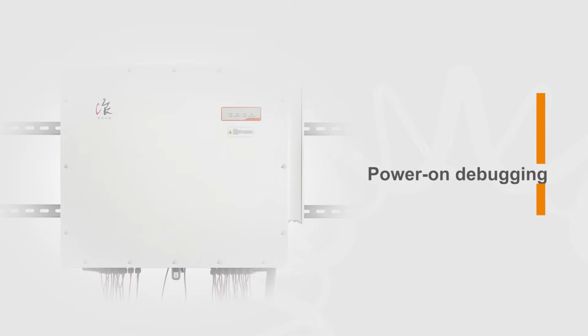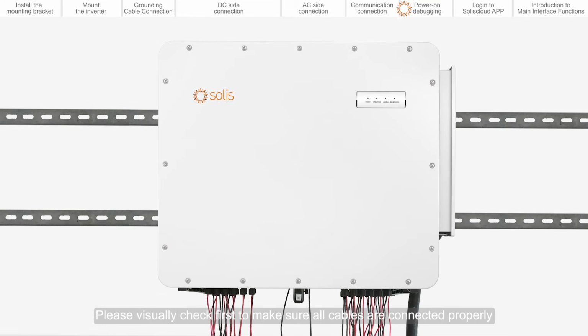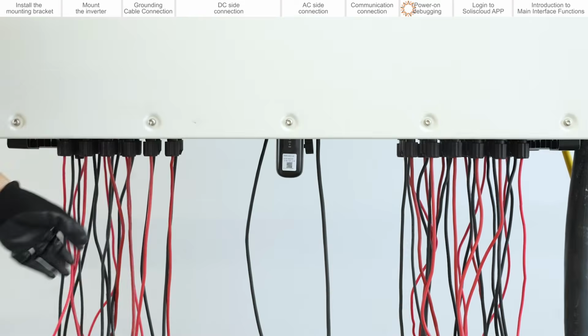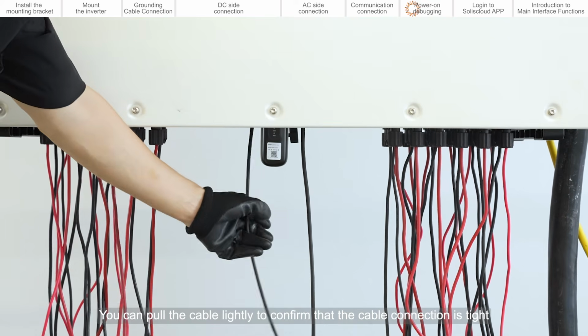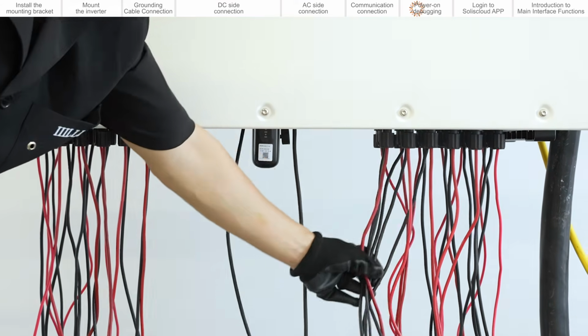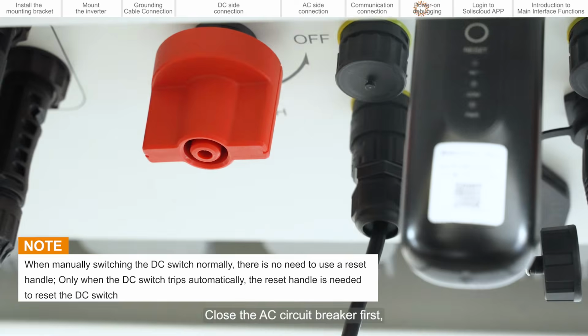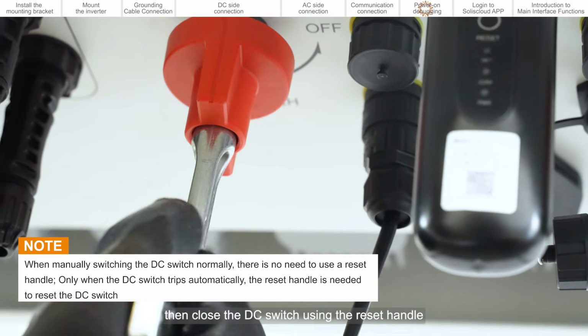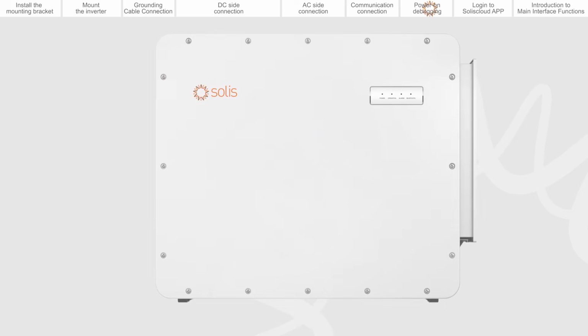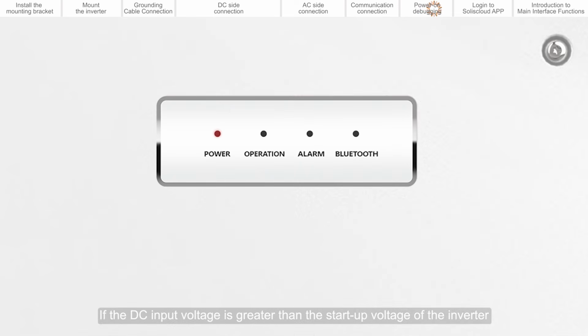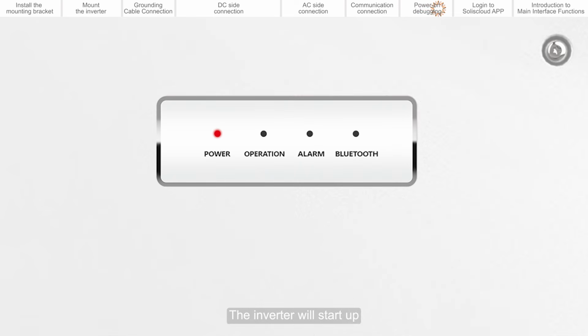Power on debugging. Please visually check first to make sure all cables are connected properly. You can pull the cable lightly to confirm that the cable connection is tight. Close the AC circuit breaker first, then close the DC switch using the reset handle. If the DC input voltage is greater than the startup voltage, the inverter will start up. After the local mandatory delay ends, the inverter will start normal operation.